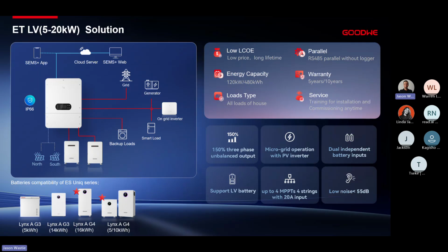Next is the MPPTs. With the ETLV, we have up to 4 MPPTs, so on a 20 kilowatt unit, 4 MPPTs with 1 string each. Every single string is completely independently monitored and controlled, meaning we can have 4 different roof orientations or 4 different roof angles and have all of our panels completely independently monitored and controlled so that we can get the most efficiency out of the PV.